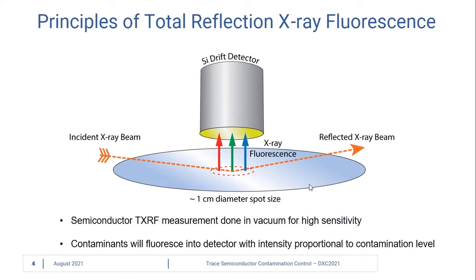The wafer moves on a stage underneath the detector, and this is how we're able to map the entire wafer surface and define our incident angle. Something different with the semiconductor TXRF versus the benchtop models is the measurement is also done in vacuum.